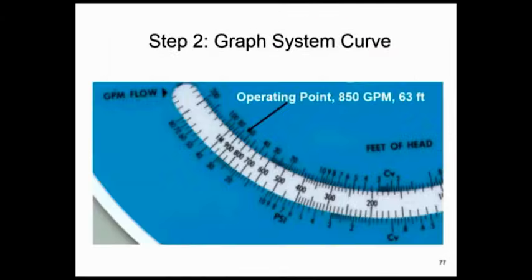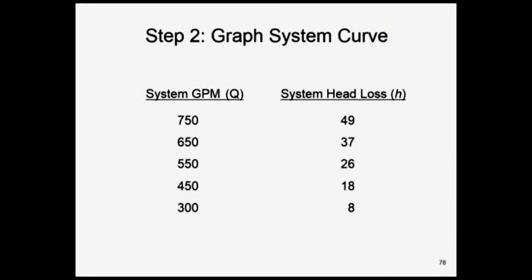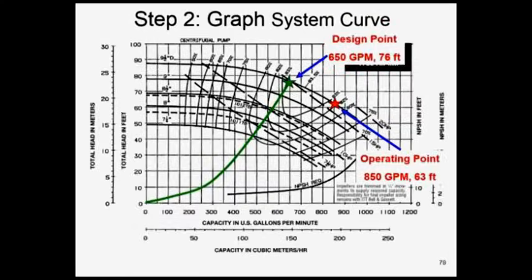Let's go to scale 5. 850 at 63 feet. Remember that? Right off the CV curve, right off the square function curve. Let's pull off the points for a real system curve, not the one on the drawings. So we know it's 850 at 63. So let's just pull them off. At 750 it's 49, at 650 it's 37. So we just did that square relationship. You can pull it off your little iPad or however you want to do it, off your system curve on scale 5. And we're going to come up with the system numbers. These are the real numbers based on your gauge readings, the 63 feet of head. Now what do we do? We very simply take those and we plot them onto your pump curve. I'm going to plot them right now in red. There you go.